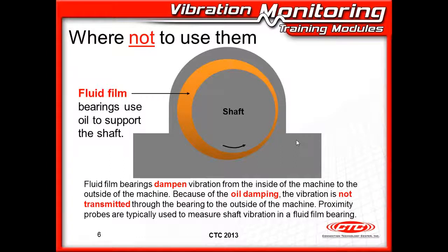Where not to use them? Fluid film bearings. Our fluid film bearings have got oil in them, as outlined here by the orange, and because of that oil, they have a large damping. So that oil is providing damping, and the vibration of the shaft does not transmit very well to the outside of this machine case. In fact, maybe the first measurement you get with an accelerometer is when the shaft actually hits the case of the machine. So be very careful on a fluid film bearing. Know that you're not going to get the true amplitude because of the damping of the fluid there.